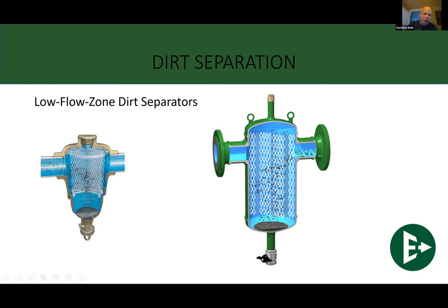After that, it's just a quick drain out the bottom, and then away it goes. Really effective way to clean the dirt out. And because it's not relying on a screen to catch the dirt, it's using physics to catch the dirt particles, we can get all the way down to about 5 microns. Now, 5 microns in size, if you take a human hair and split that into about 7 pieces or so, that's going to be 5 microns. So really small particles can be caught in this type of application with regards to a dirt separator.